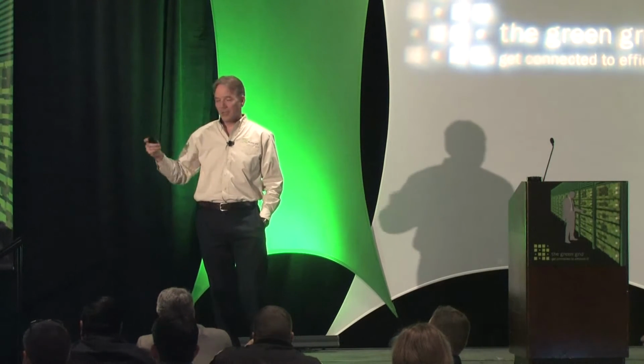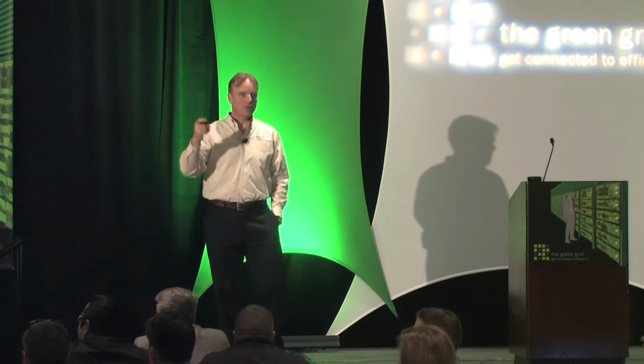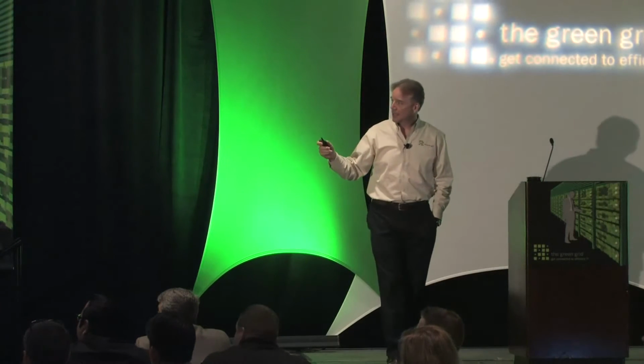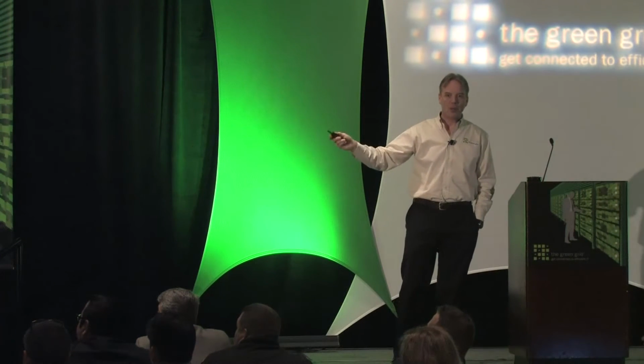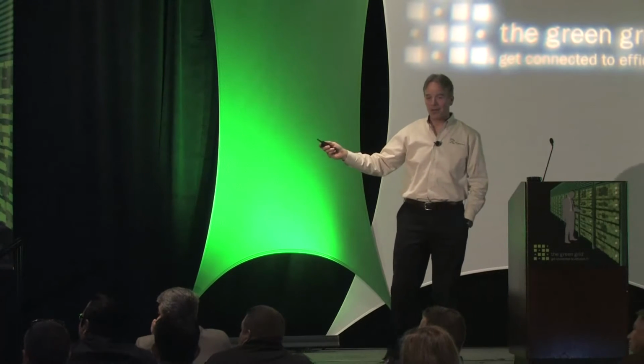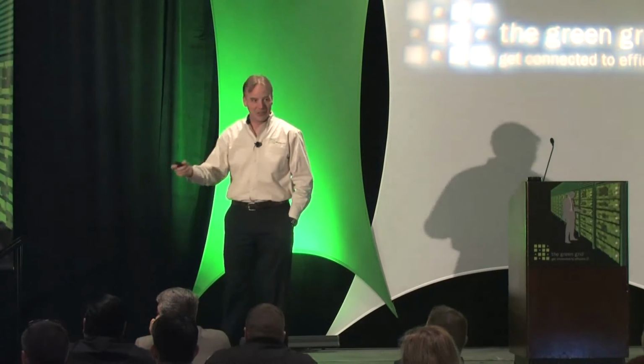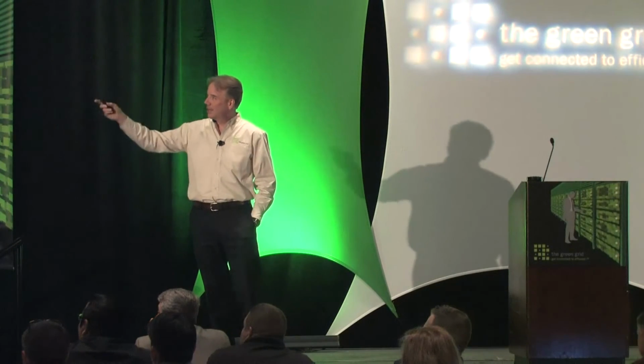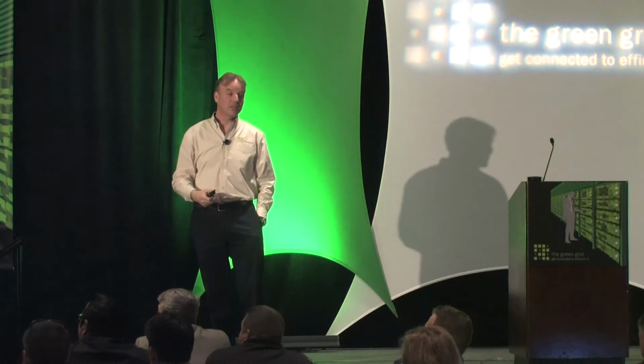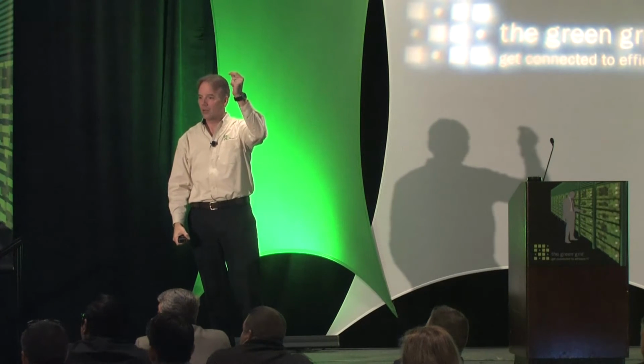Okay, so there's also some lessons learned in there, and I'll explain that a little bit later, but the scale was what was important. All right? And this is the white space, and notice the white. Part of the DCMM talks about lighting. We chose white racks instead of black because I didn't need as much lighting, right? It's easier for the techs to do their work, etc. And also just notice the above, everything's decoupled. Rack and roll literally is rack and roll. It rolls into a position, we plug in the network, we plug in the power, and it goes.